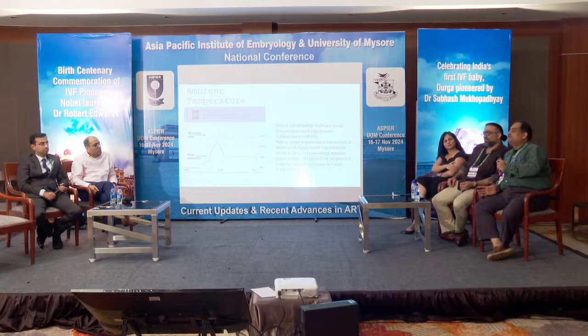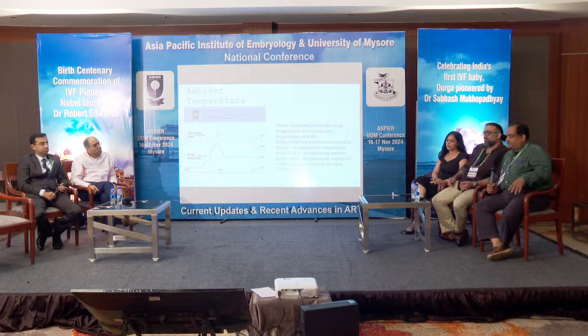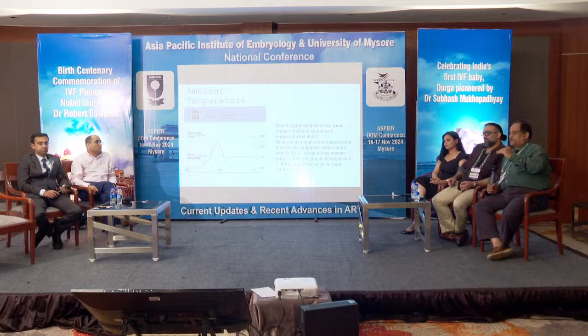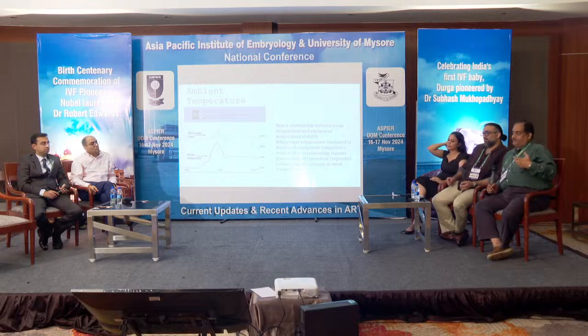It's of very high importance. Ambient temperature should be assistive. Whatever incubators or heating instruments we use, they do not have a cooling possibility. So the ambient temperature should be bare minimum 10 degrees below the set temperature of your heating incubation system. That puts my maximum room temperature at 27. But at 27, some people might feel uncomfortable. So the ideal ambient temperature is between 22 to 26.